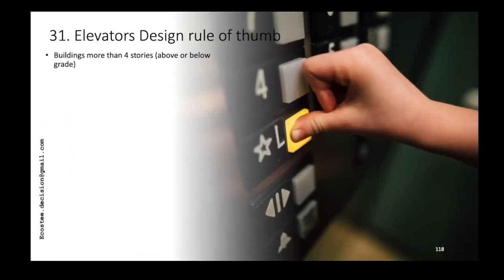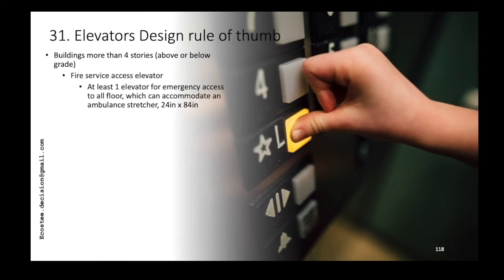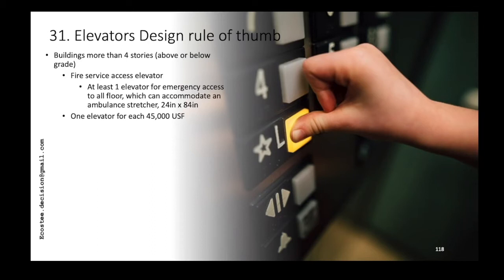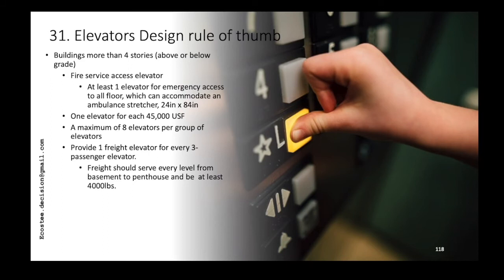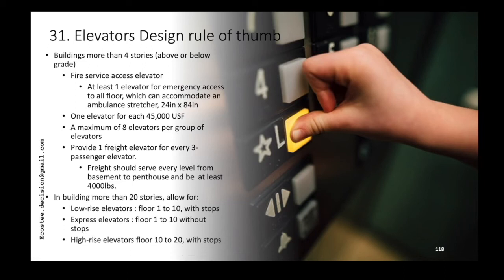Beyond the four-story threshold for requiring an elevator, you may also need an additional elevator for fire service access. As a rule of thumb, provide one elevator per 45,000 usable square feet, and a maximum of eight elevators per elevator bank. For large buildings, split them into groups — for example, one group on the northern part and one on the southern part. Also provide one freight elevator for every three passenger elevators, and the freight elevator should carry at least 4,000 pounds to transport mechanical equipment between floors.